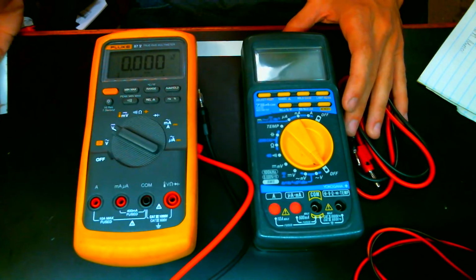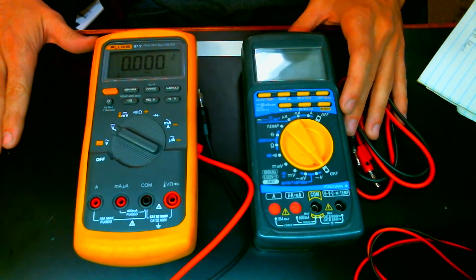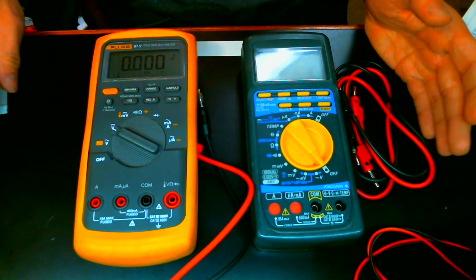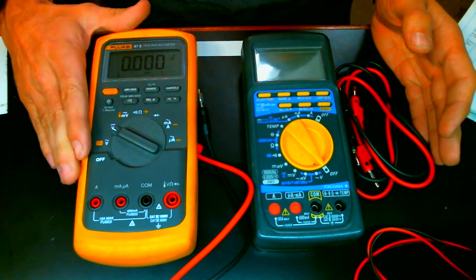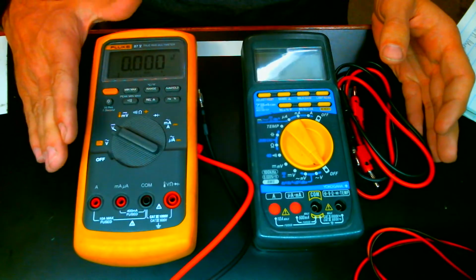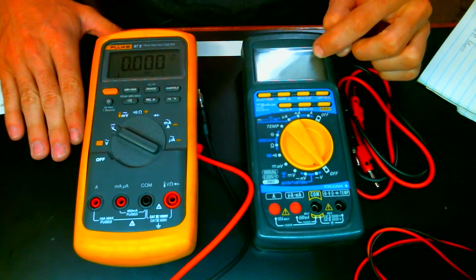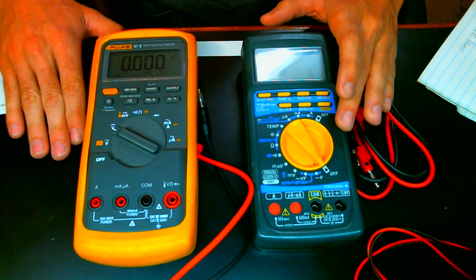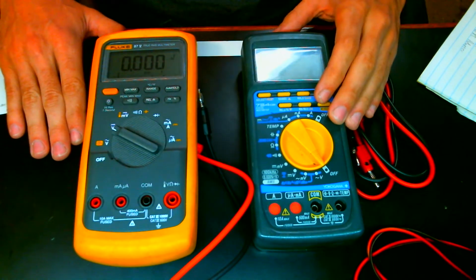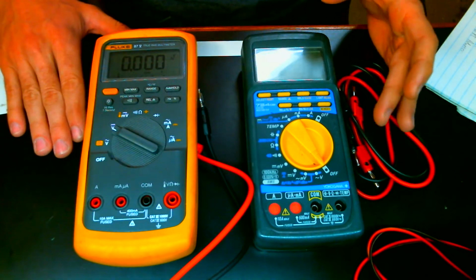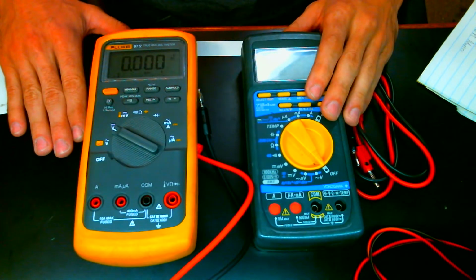Stepping up a little bit from there is when you get into verifying measurements. This is where you want to see if your meter is accurate or not. This is where having an accurate reference is absolutely necessary, because you want to know that what this meter is telling you is true. Now, realize that we are not going to have any kind of traceable certification on this. You're mostly going to just use it to say that I'm using this meter and I know it's good because I've compared it to another known meter.